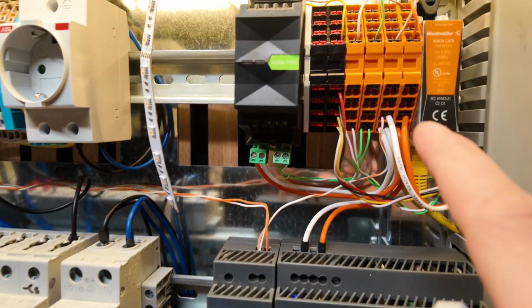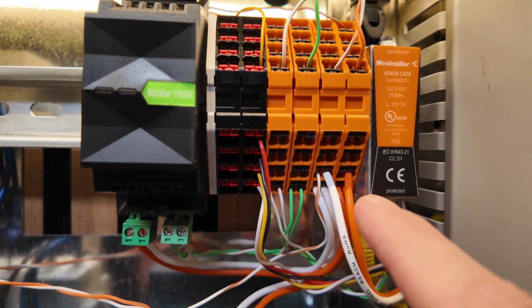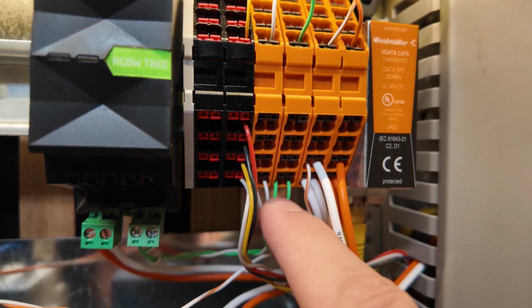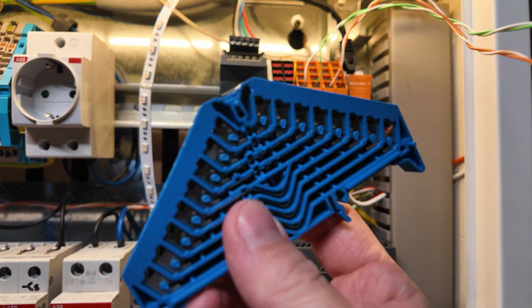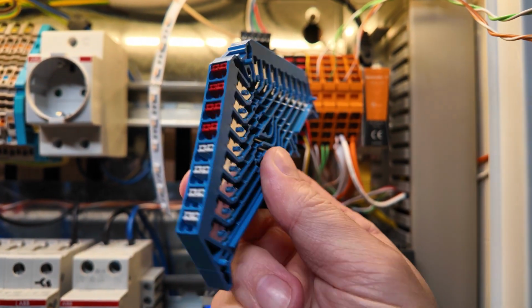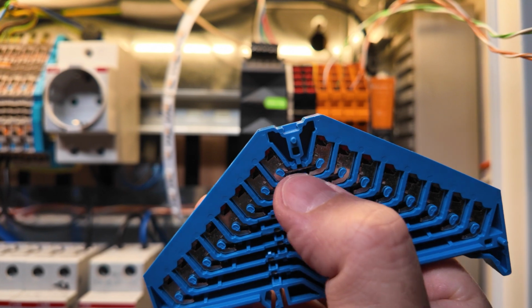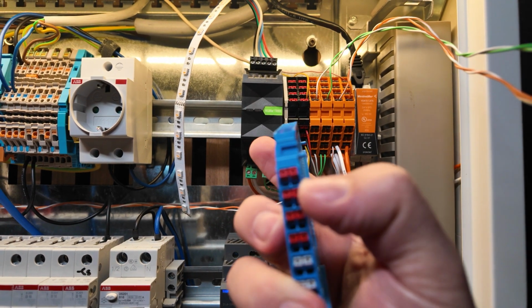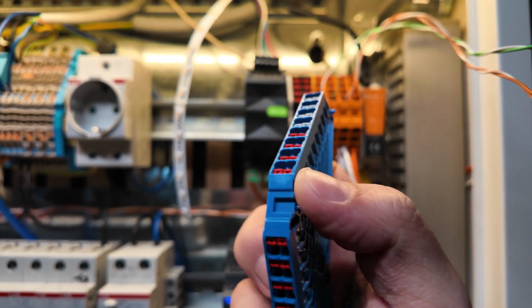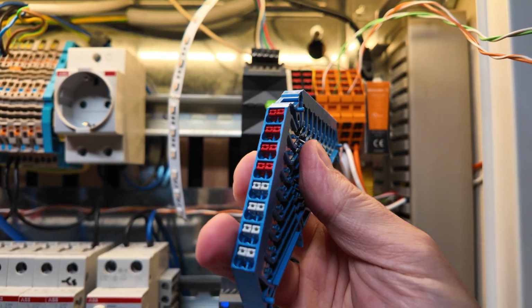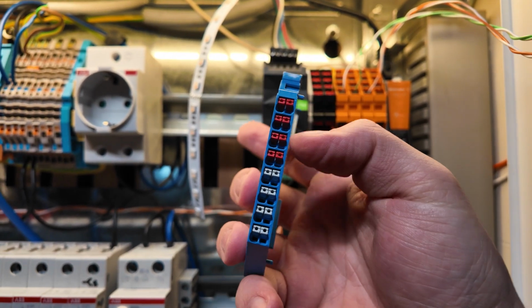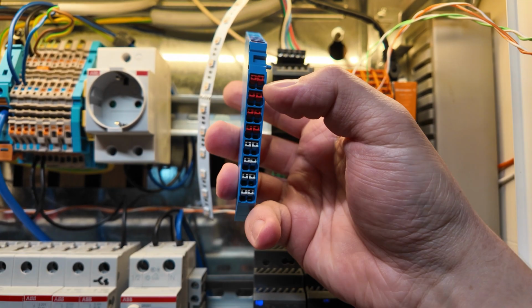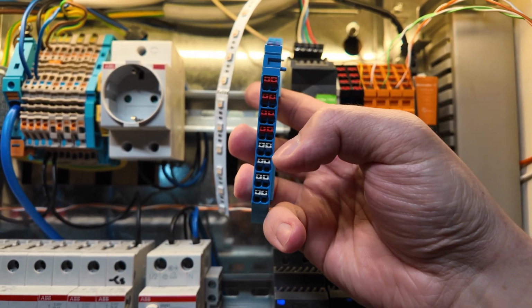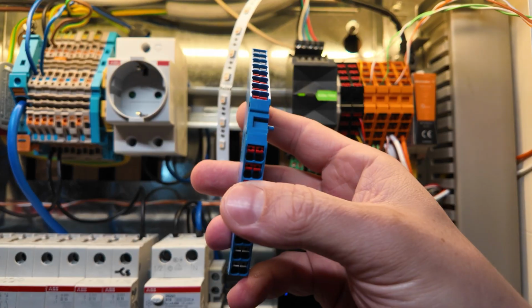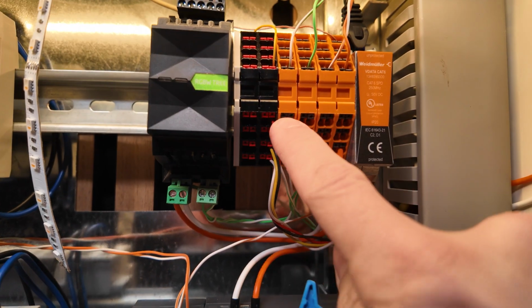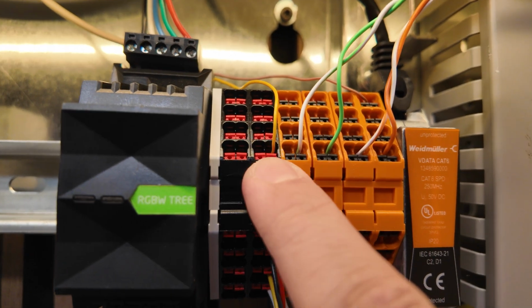These clamps are perfect, same as for the orange one here, to distribute 24 volt or also the tree bus line. There are other versions like this one here with 8 inputs, and here only the first row is connected to the first row. So these two up here to these two here. And then second row to the second here. This is perfect for putting a CAT cable with 8 inputs onto the cabinet. And then we could have 7 window contacts, for example, back to the digital inputs here. The small version of this one here is the black clamp here. I'm using this for 24 volt inputs here.